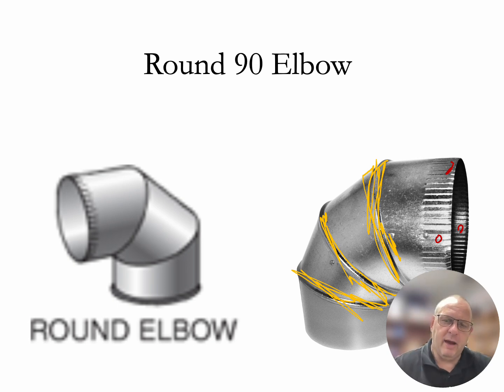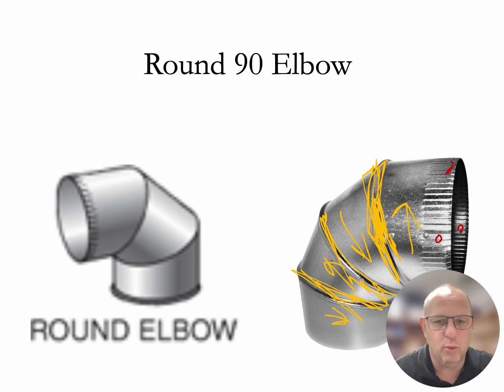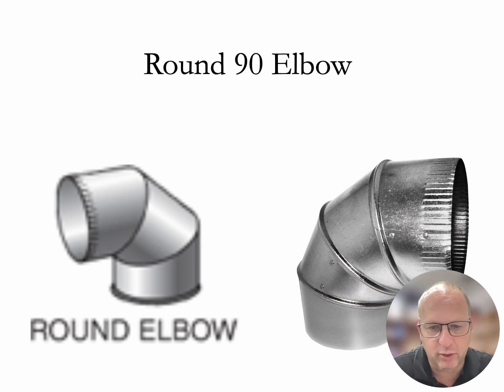Just remember that we have our 3 screw holes to keep them in place. We can take this 90-degree angle and adjust it in any way, shape, or form. And that has to do with these places that we're going to seam right here, these seams. We can move this ductwork like we want to. We can take that direction, this one this direction, and this one that direction, and then opposite. Any way that we want to move this elbow, we can do that with the design that we have on it to make sure that we have the correct positions. Remember your 3 screw holes. Remember your mastic that you're going to be using to seal this duct up.